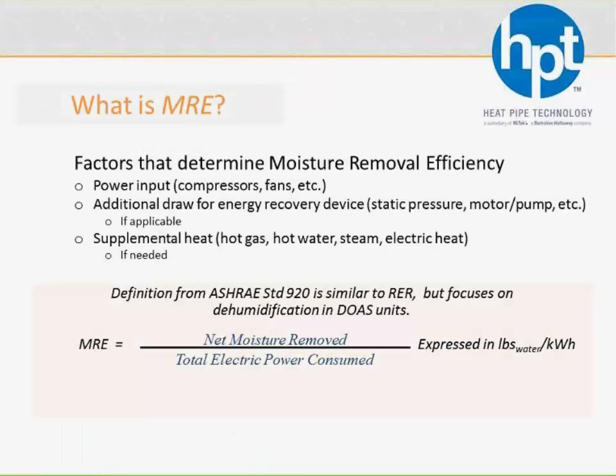So what is MRE? Excellent question. MRE is your moisture removal efficiency. I don't want to say EER is no longer a concern, but it's not going to be how DOAS equipment is measured or standardized moving forward. It's all going to be based on how much moisture is being removed. So we're talking MRC, or moisture removal capacity, or pounds of water per hour that the DOAS unit is able to remove. But MRE takes it one step further and doesn't just look at how much is being removed, but how efficiently it is removing it.